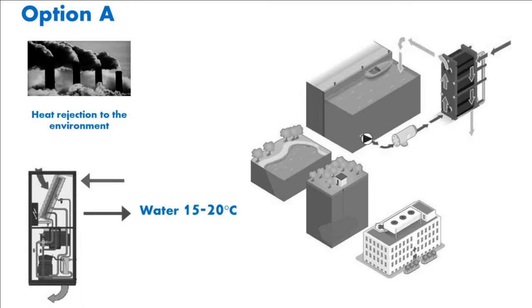The temperature of the liquid at the outlet of the close control air conditioners is about 15-20 degrees and does not allow heat recovery without the use of heat pumps. In turn, investments in heat pumps are not profitable at current prices for heat supply. To discharge heat into the environment without using mechanical cooling, the free cooling modes use the sea, lakes, underground aquifers, and in most cases ambient air. Thus, we not only throw money down the drain, but also damage the environment.